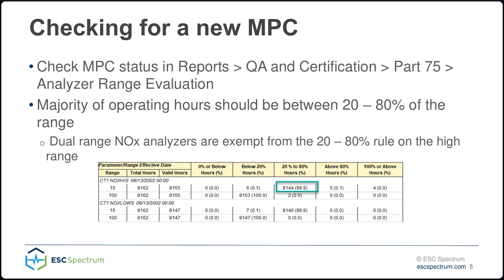If you look where it says CT1 NOx high S and it says 15 and 100, it shows that 100% of the hours are below 20%. The NOx low S on the 100 span — that does not apply. What I'm looking for is that the 15 span is 20 to 80%. I would look at that and say, okay, we're good for the year; I don't have any recommendations for changing. But if maybe 51% is 20 to 80 and 49% are elsewhere, technically the majority is in 20 to 80 but this could still be adjusted. You kind of have to decide for yourself based on how your site operates what actually makes sense.